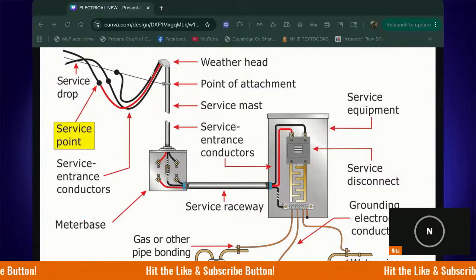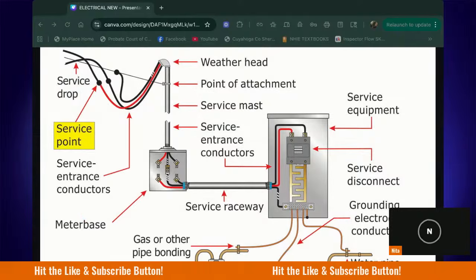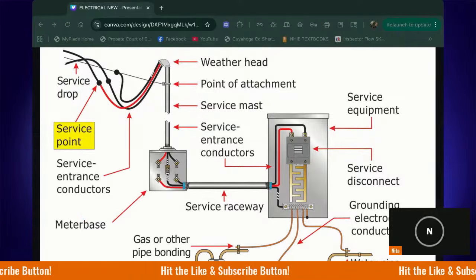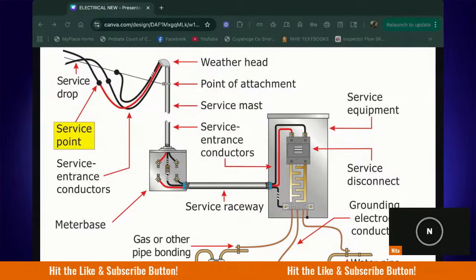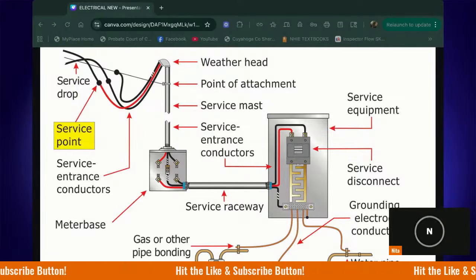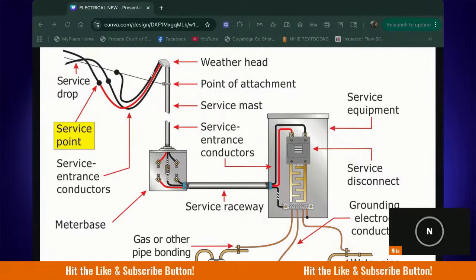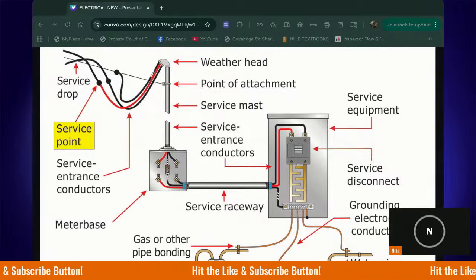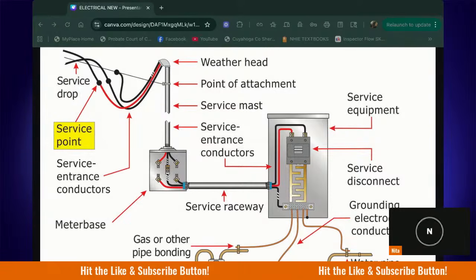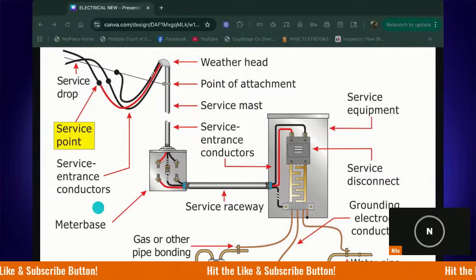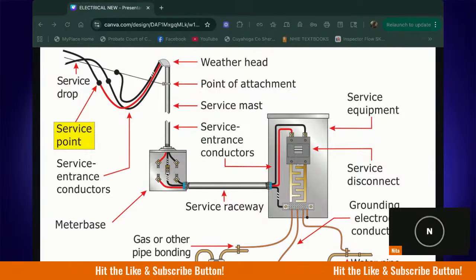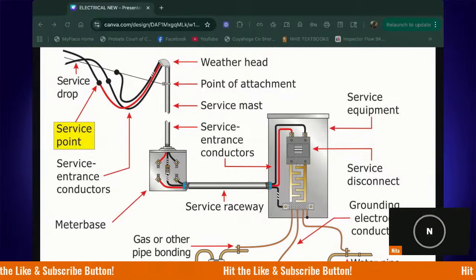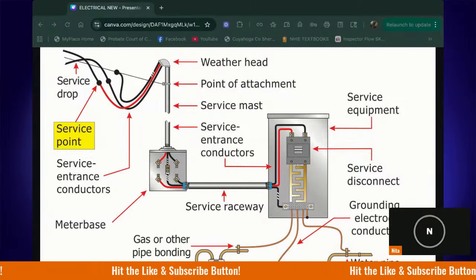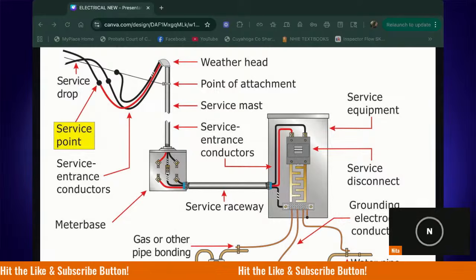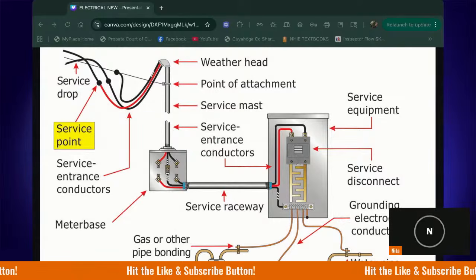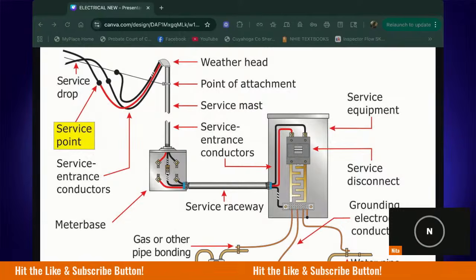Meter bases: there's a shape that gives you sort of a clue about the power of the house. Back in the day, the meter bases used to be round, and that meant that the house had a service of about 60 amps, which was way low. The square meter bases like this are the newer standards. This indicates a service of about 100 amps. And then there's a rectangular meter base that denotes a service of 200 amps on your newer homes and things like that.